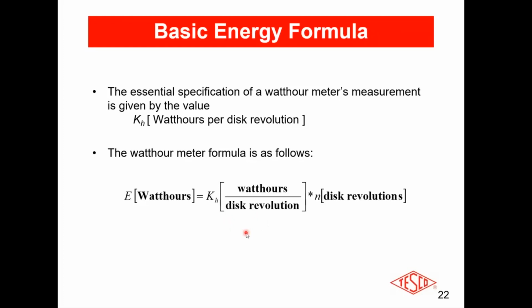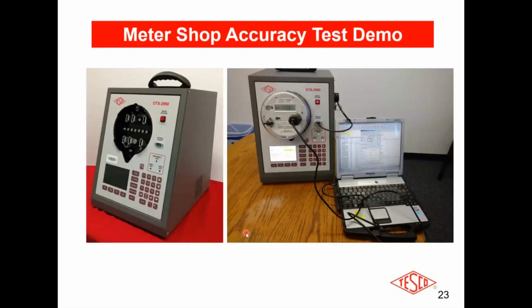Between every pulse, for every pulse, it is a certain number of watt hours per pulse. Count the pulses, and you can give a meter. So we're doing the same thing now with our electronic meters. You simply put in your pickup or your probe, your combination pickup and probe, and you can do a meter test, because you just count the pulses and you know exactly how much energy is being drawn.